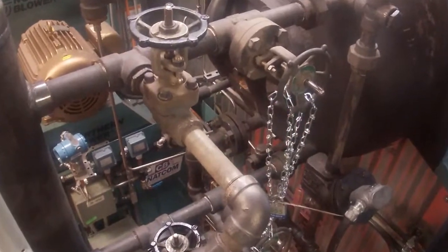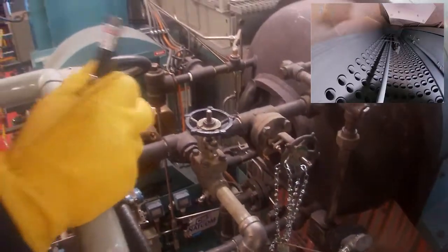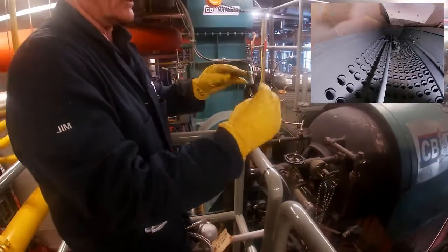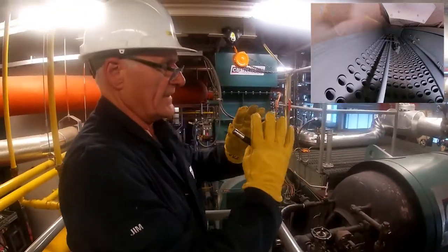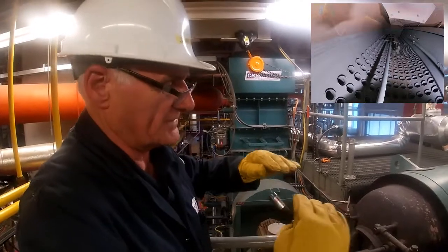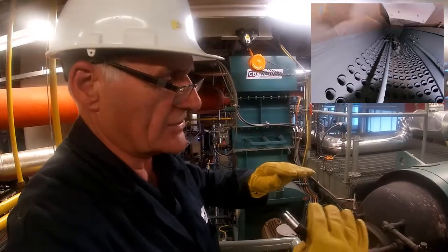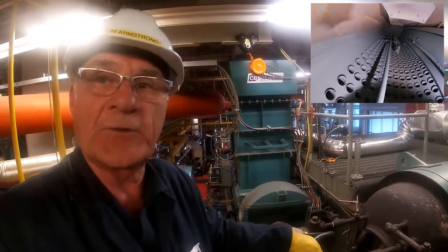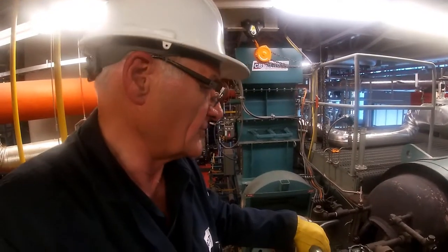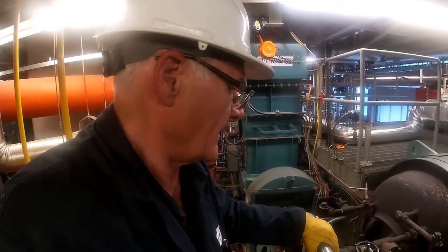And again, at that feed water inlet, the pipe goes into the boiler, goes down to the far end, and is blanked at the end, and then it's got holes. The holes are set such that they don't blast down into the tubes. They actually blast out, so they're just over top of the tubes, so they don't interfere with the downcomers and the risers. Okay, that's very important to make sure that's done properly.